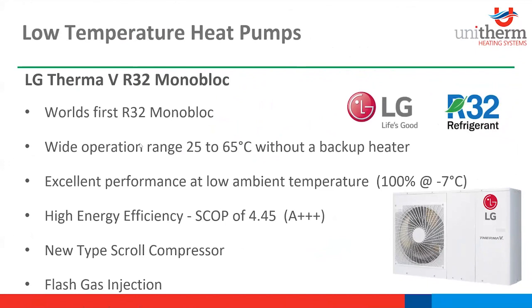Now, I'm sure you've all heard of R32 lately. What is it? It's basically the fifth generation refrigerant, and it is replacing R410A. R410A is being phased out by 2025, mainly due to its high global warming potential of about 2088. Whereas R32 has a significantly lower global warming potential, about 66% lower, at 675.